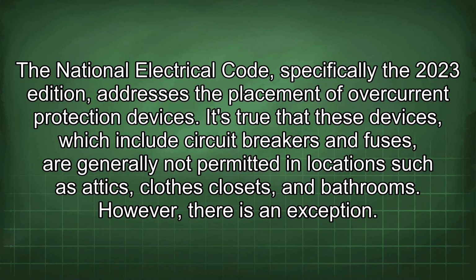The National Electrical Code, specifically the 2023 edition, addresses the placement of overcurrent protection devices. It's true that these devices, which include circuit breakers and fuses, are generally not permitted in locations such as attics, clothes closets, and bathrooms. However, there is an exception.